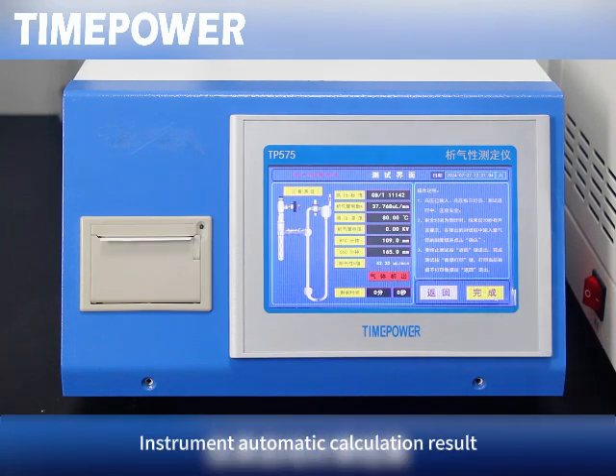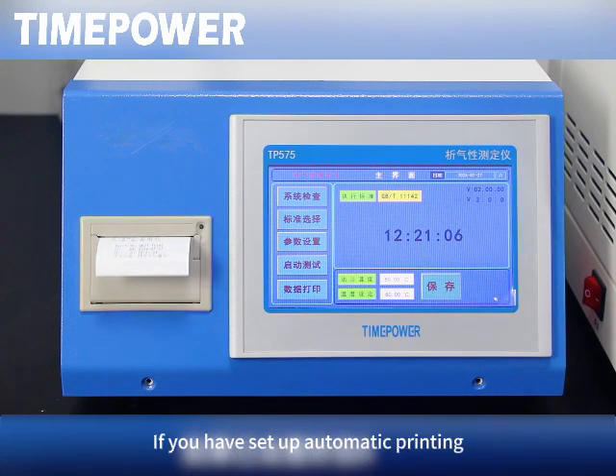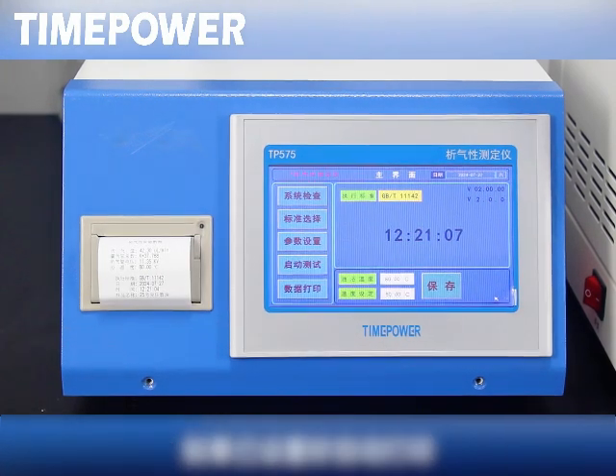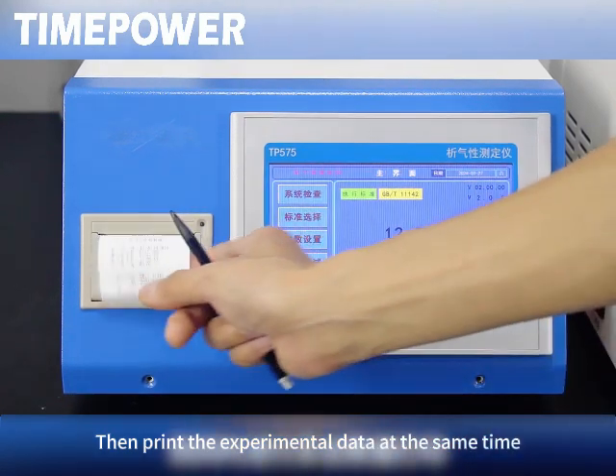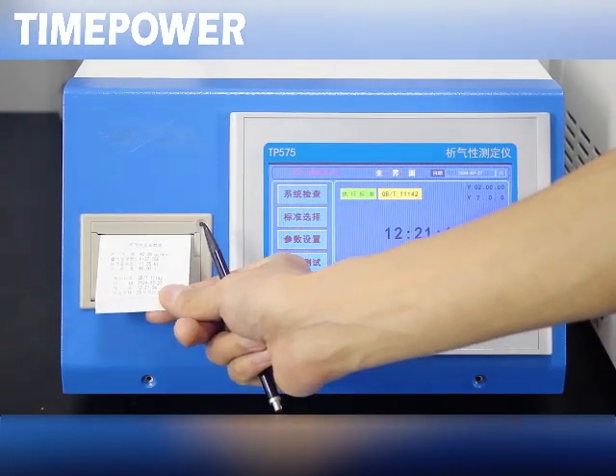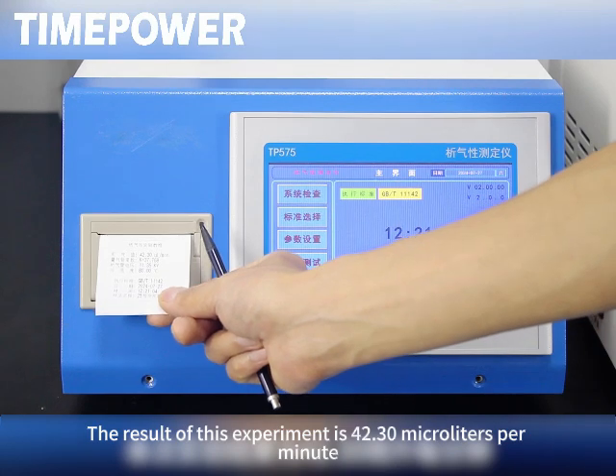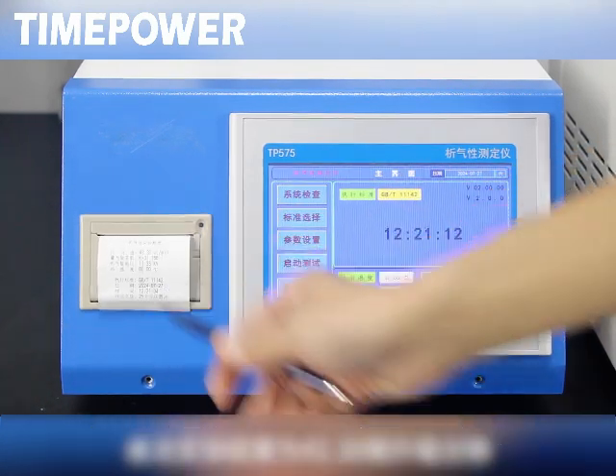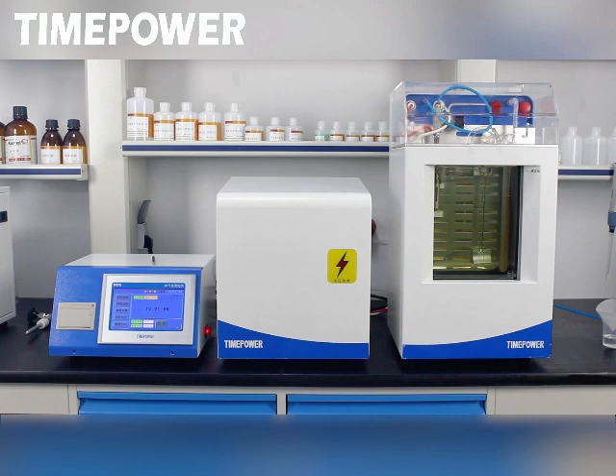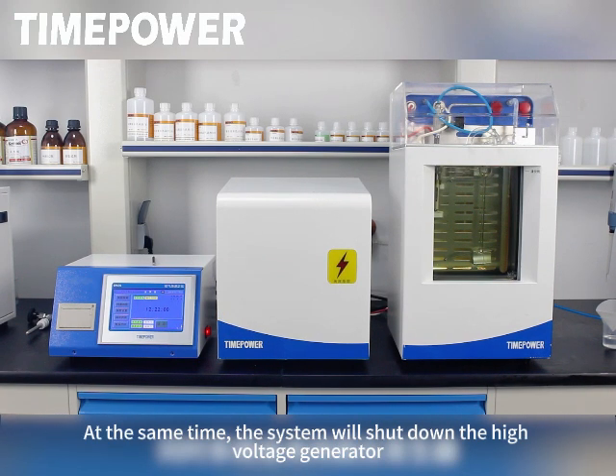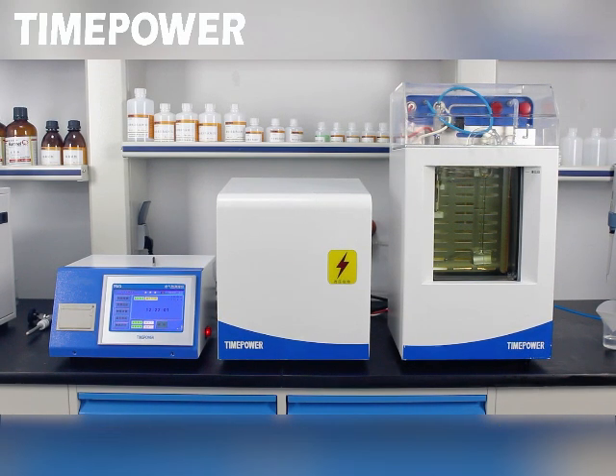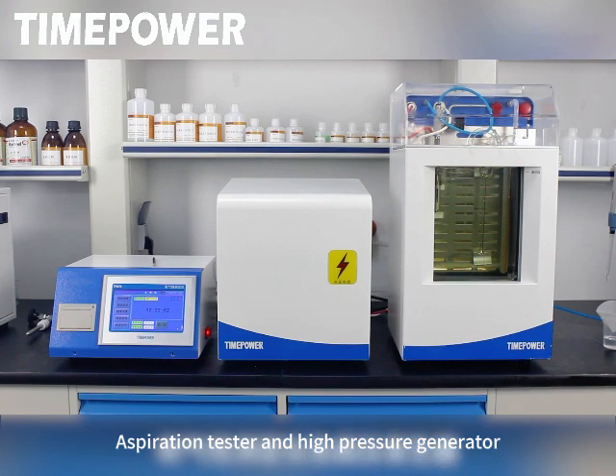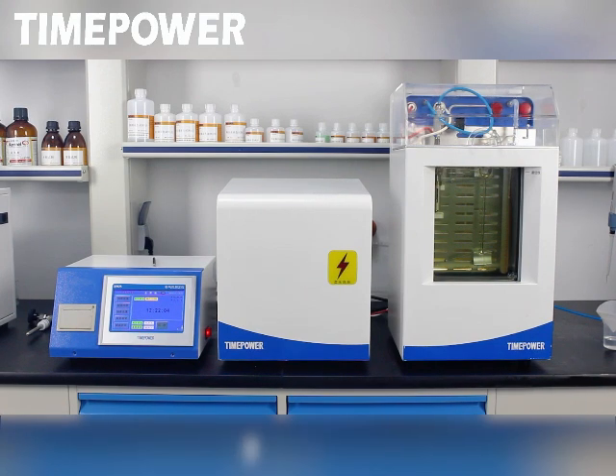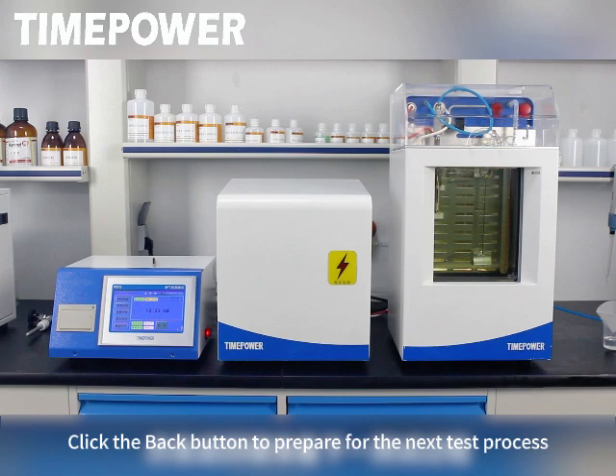The instrument automatically calculates the result. If you have set up automatic printing, the experimental data is printed at the same time. The result of this experiment is 42.3 microliters per minute. At the same time, the system will shut down the high voltage generator, aspiration tester, and high pressure generator. The lights go out. After the test is completed, click the back button to prepare for the next test process.